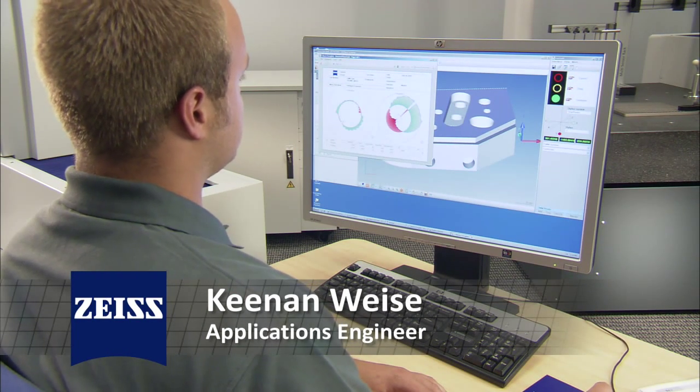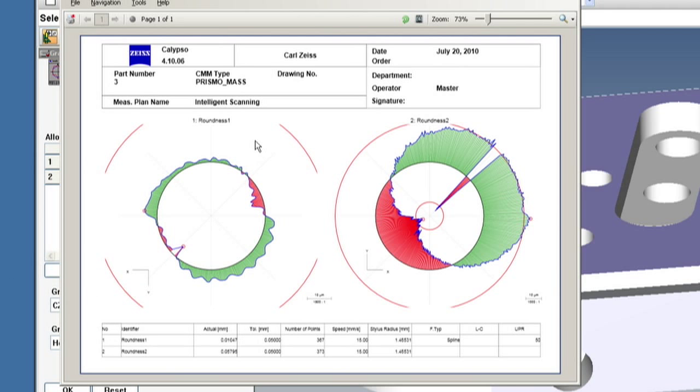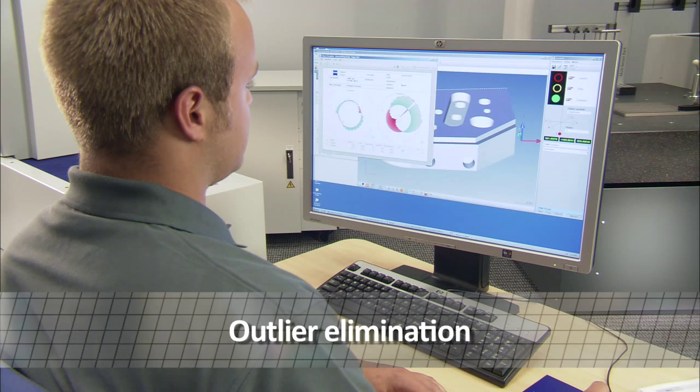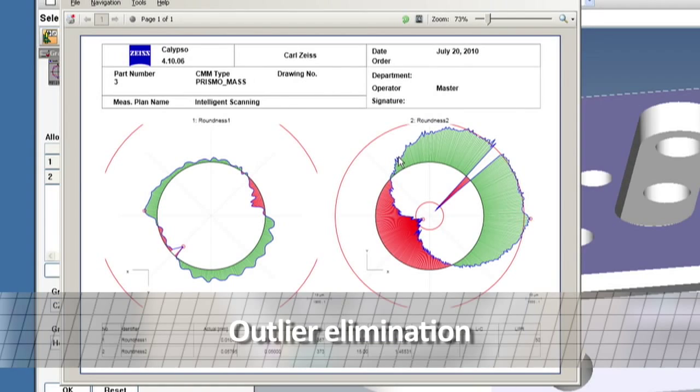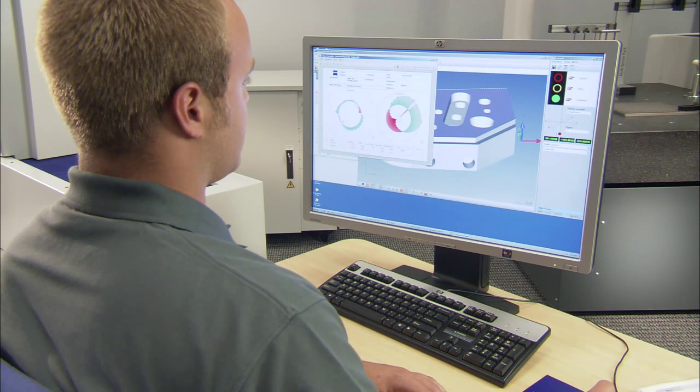Here we can see two plots. This is the roundness in the exact same location in a cylinder. You can see the second roundness has what we call chattering, very defined peaks and valleys and also an outlier that was purposely put in there.